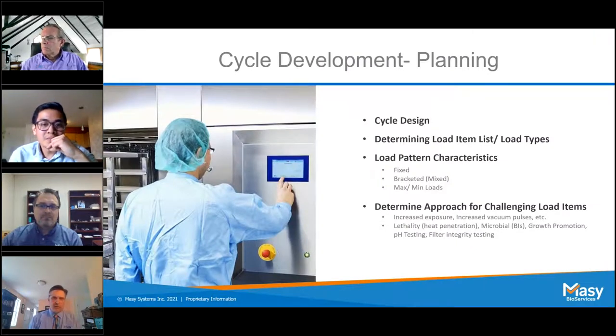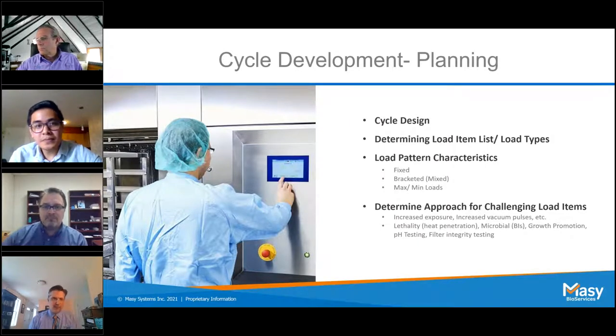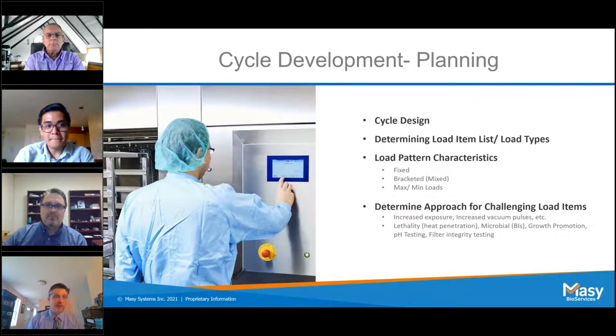Okay. So like protocol development, you'll need to know what your sterilizer is capable of. The control of it is going to be extremely important. You need to know how it's developed. If you're trying to meet specifications, especially the specifications that we were talking about before inside of EN 285, there's a lot of little things inside of there that you need to be able to meet. To give you an example, the equilibration time, depending on the size of the sterilizer that you have, you either have 15 or 30 seconds to be able to hit that. Cycle development is extremely important in that case.